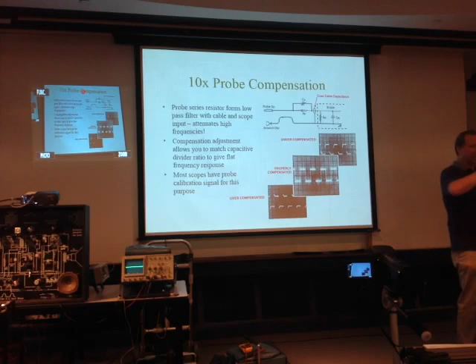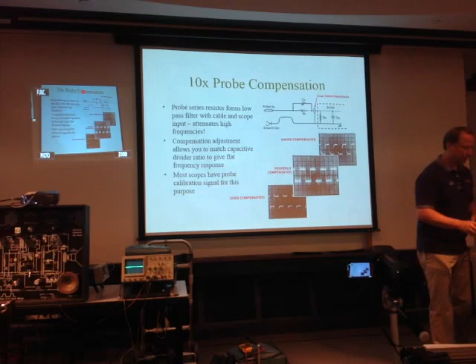So the real key, if you're looking for a probe to match your scope, is that the probe will have a rating on it for what input capacitance range it can be compensated for. So we'll say the compensation range might be 10 to 30 picofarads or 15 to 30 picofarads or something. You have to know what your input capacitance is on your scope, right on the front panel. So buy probes that can be compensated for that capacitance.